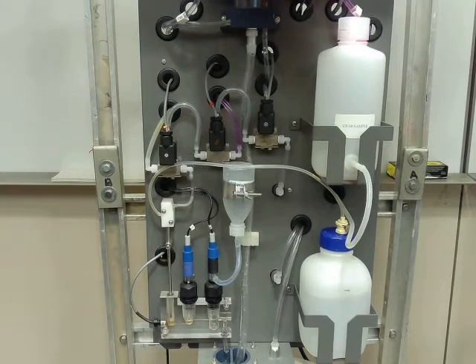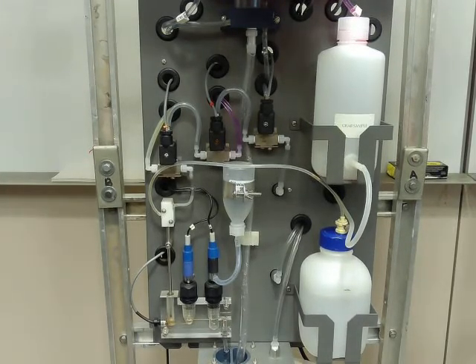One issue that can happen is that as that solution dries out, if you spill a little bit, you'll see it happen quickly, you get a white precipitate. If that precipitate starts to form inside that tubing or inside the actual electrode itself, it'll definitely affect how well it can flow into your sample and perform its job. You'd want to flush that out and replace that solution.